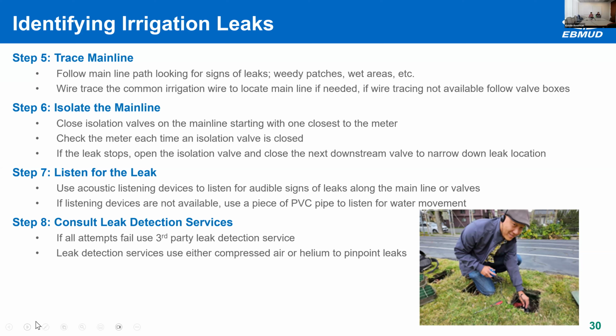So we open that first valve up, go to the second isolation valve. We close that one. The leak stops. So we know we still have to keep going down that line. So we go to the third isolation valve on the path. We open the second one back up, and then we close that third one. The leak is still happening. So now we have found that leak between that second isolation valve and that third isolation valve, which again, helps us narrow down where our leak is. And if you do have to utilize leak detection services, you have at least narrowed that path down. We'll talk a little bit more about that on step 8.